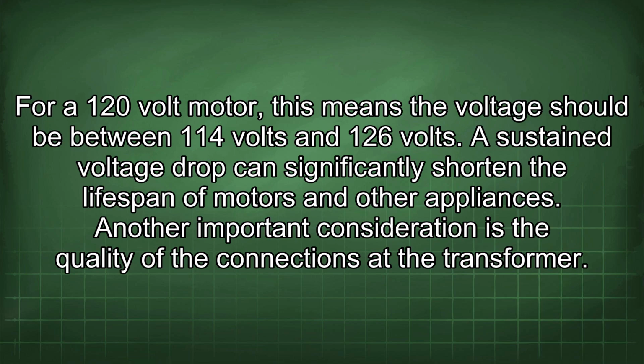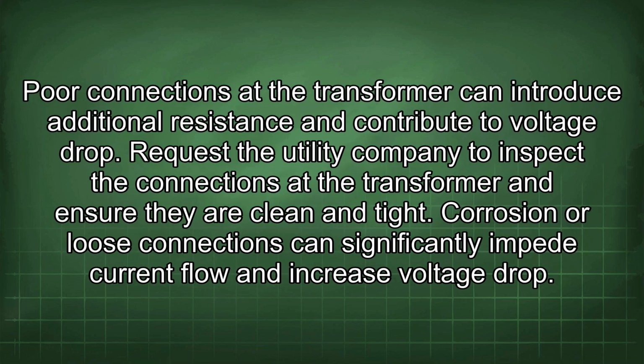Another important consideration is the quality of the connections at the transformer. Poor connections at the transformer can introduce additional resistance and contribute to voltage drop. Request the utility company to inspect the connections at the transformer and ensure they are clean and tight. Corrosion or loose connections can significantly impede current flow and increase voltage drop.